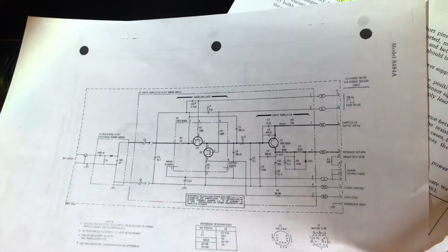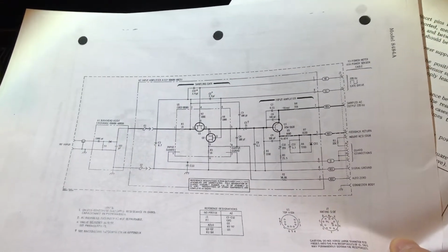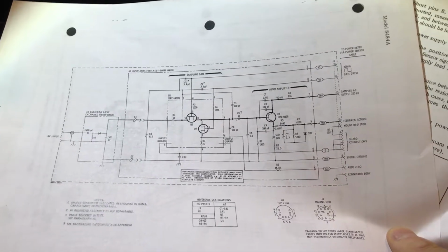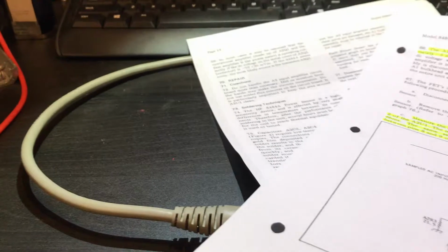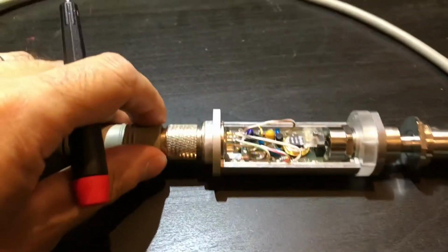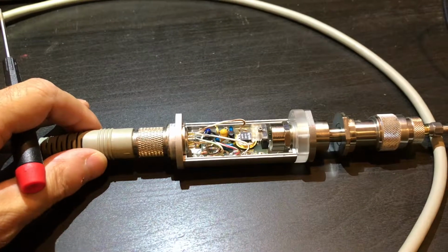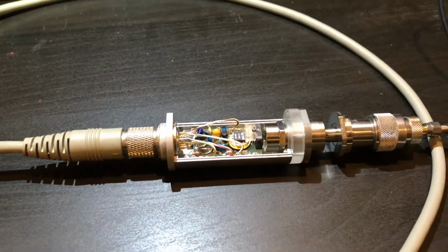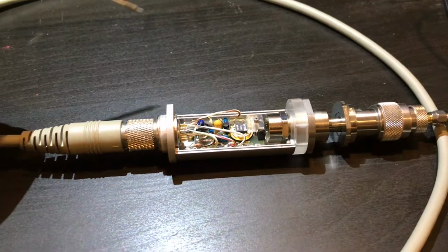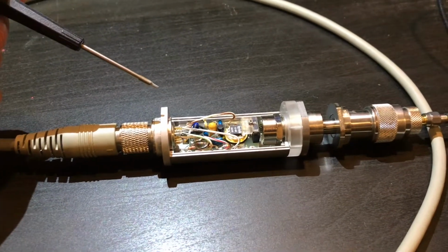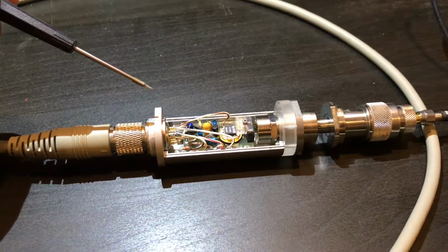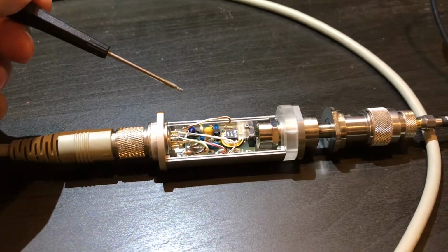It's got a schematic diagram of the power sensor itself. I know this is kind of dark. The lighting in this room isn't very good, but if you just follow along with me, it's got a schematic diagram with a pinout, and it's also got lots of information about the way the sensor works, theory of operation, and a section for troubleshooting. So we're going to walk through some of the things in that manual and take some readings, and we can determine whether it's got a bad sensor or if there's some other problem. I've got my suspicions as to what the problem is, and we'll get into that a little bit further on down.